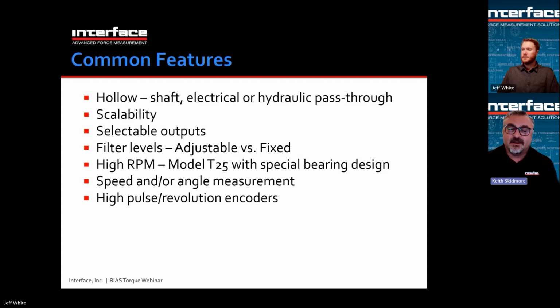Speed or angle measurement is interesting. For measuring power, you need not only a torque, but a speed measurement. It's nice if that's integrated into the torque sensor. Also angle, doing a valve test or some kind of a test where you're measuring torque versus a specific angle.